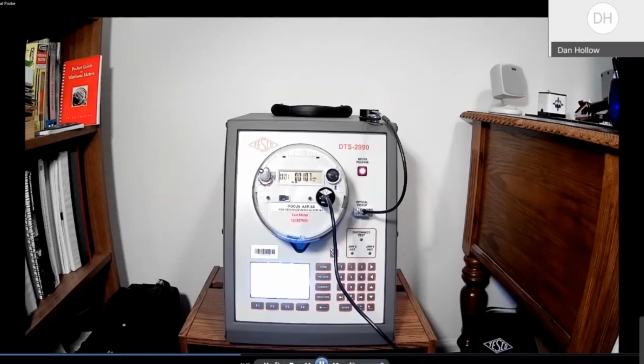So we're going to go ahead and initiate a communication session. When you communicate optically with a meter, it is not physically connected between the meter and the laptop or desktop being used. It is basically an infrared light communicating with the meter using an infrared LED and an infrared transistor. So it's serial communications with no physical electrical connection between the meter and the laptop or desktop reading. So I'm going to put this into the online view, which is a continuous communication with the meter.